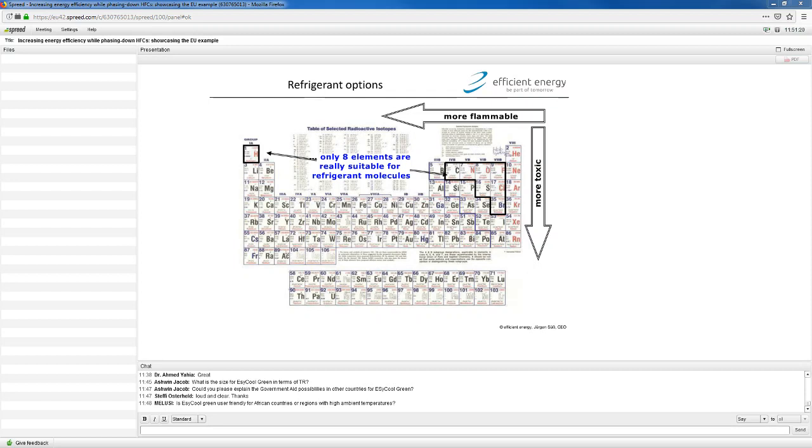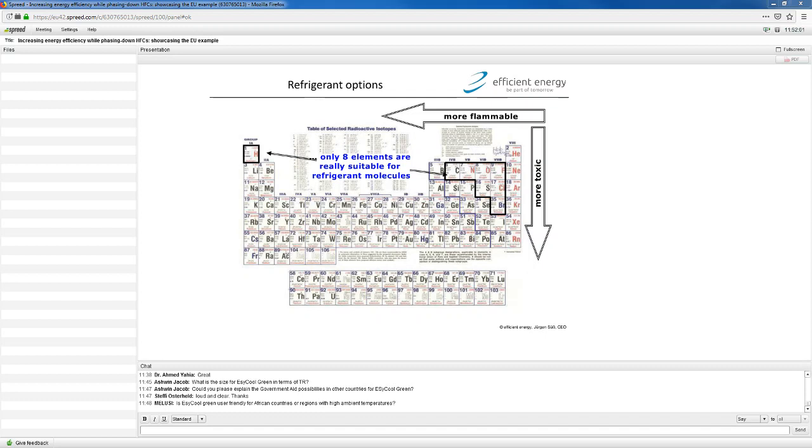It would be a shame if hydrocarbons wouldn't burn because then we wouldn't be able to do barbecue and stuff. If you go down, things get more toxic. That's why in the beginning, in the 1930s, people went to CFCs, which was carbon, fluorine, and chlorine, and that of course had the problem with the ozone depletion. When the chlorine was out, now we talk about global warming, so now we go to HFOs, which are oxygen, fluorine, carbon, and a little bit of hydrogen, and then the compromise is only to say how flammable do we want to get a fluid and what do we accept.